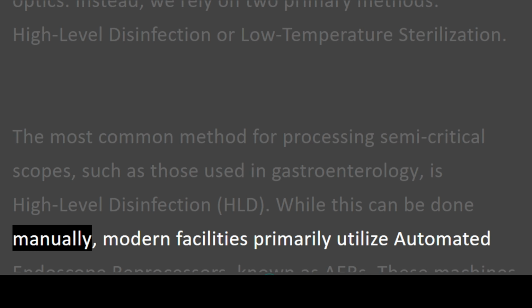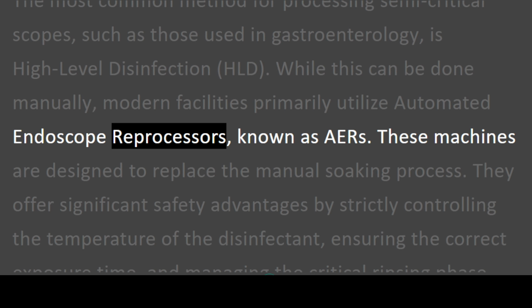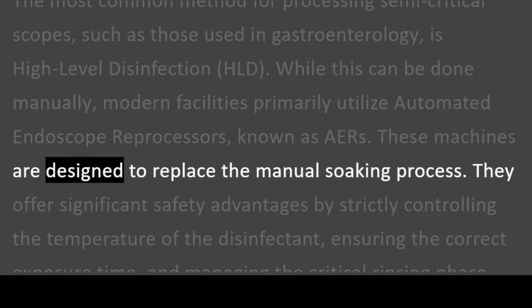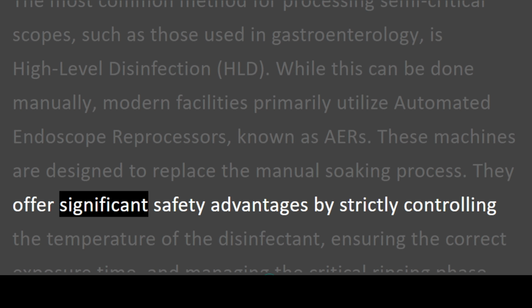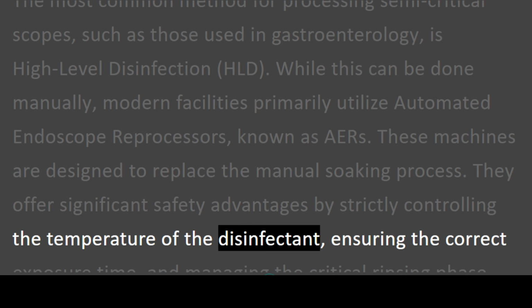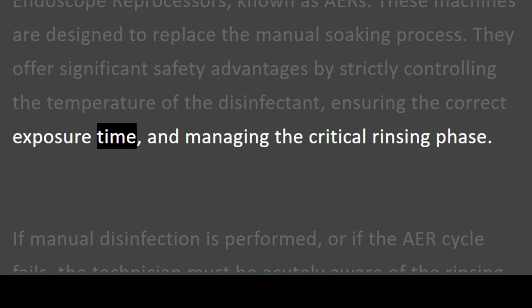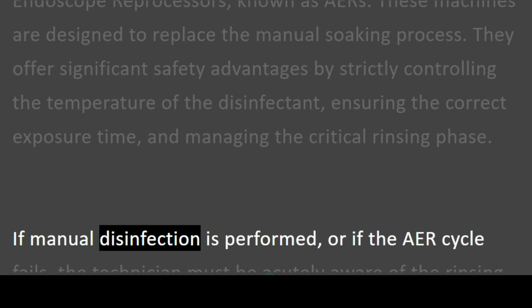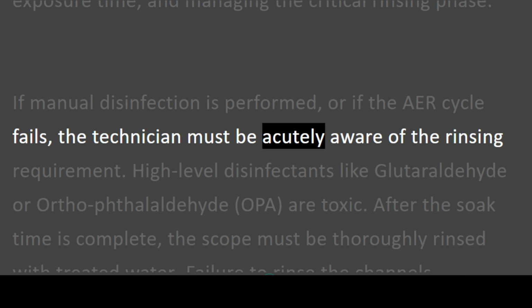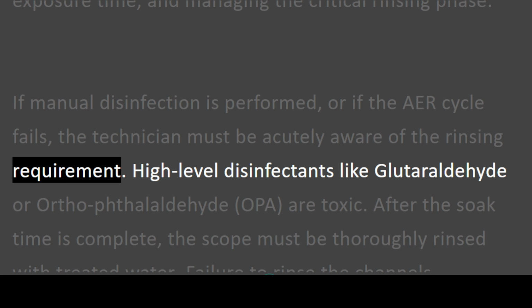While this can be done manually, modern facilities primarily utilize automated endoscope reprocessors, known as AERs. These machines are designed to replace the manual soaking process. They offer significant safety advantages by strictly controlling the temperature of the disinfectant, ensuring the correct exposure time, and managing the critical rinsing phase. If manual disinfection is performed, or if the AER cycle fails, the technician must be acutely aware of the rinsing requirement.